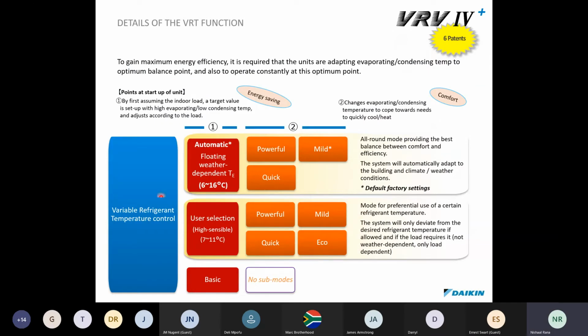So the details of the VRT function, yeah, you can go up to 6 to 16 degrees. That's on the floating weather dependent. So to gain the maximum energy efficiency, it is also required that the units are always adapting their evaporating or condensing temperature to optimize a balance point. Generally on our VRVs, 50% of the building load is actually its sweet spot where you gain your maximum efficiency.